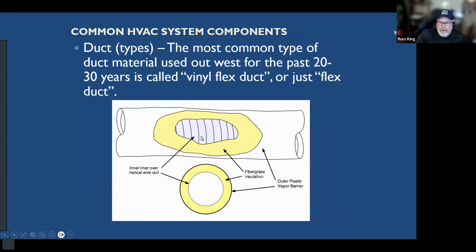So flex duct is very interesting. And it starts off as a metal wire, okay, like a slinky. Like if you took a slinky and stretched it out a little bit, and then you wrap that with plastic, and then you wrap that with insulation, and then you wrapped it again with more plastic, okay? That's basically what a flex duct is. So it has this inner liner, okay? Then it has this wire that's what gives it its shape. Then it has insulation to keep heat from conducting out of it. And then this outer wrapper is just like basically like a plastic bag. And we call that a vapor barrier.